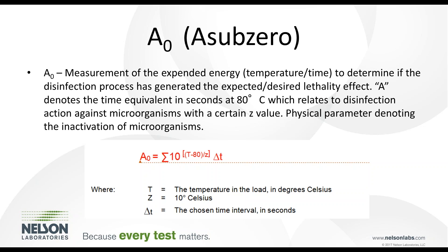Typically, you're looking for an A-0 of 600 for a non-critical device or a device that will be terminally sterilized, and 3,000 for a device that does not require further sterilization and will be used directly after. Most washer disinfectors are capable of this, but you want to confirm the washer can achieve A-0 of 3,000. This is outlined in ISO 15883.